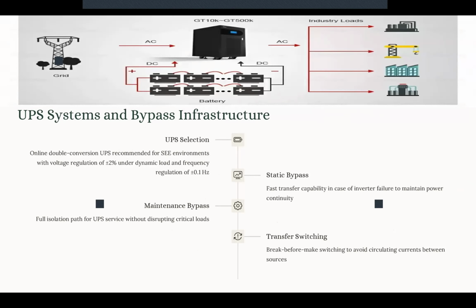In a sensitive device, we also use UPS and bypass infrastructure because it's important for us to continuously supply our load. So we need to make sure that we have a proper selection of our UPS. The recommendation is to have an online double conversion UPS for our sensitive equipment, and the voltage regulation should be within plus or minus 2% under the dynamic load, and the frequency variation should be less than 0.1 hertz. So plus or minus 0.1 hertz.